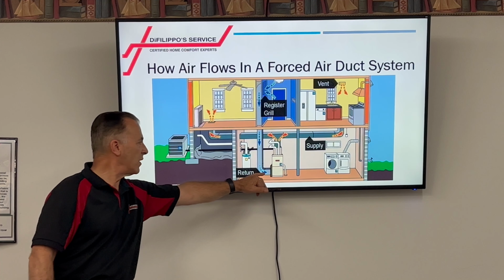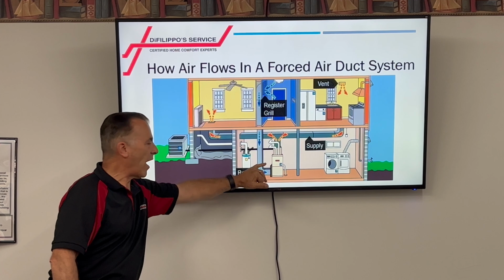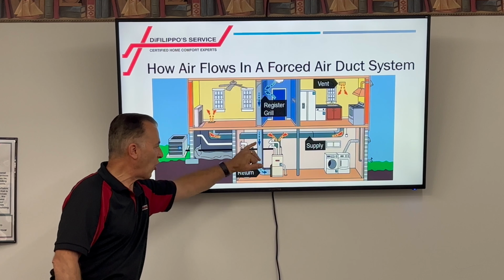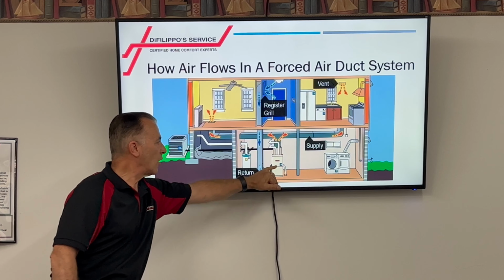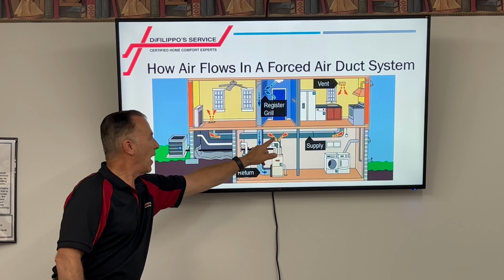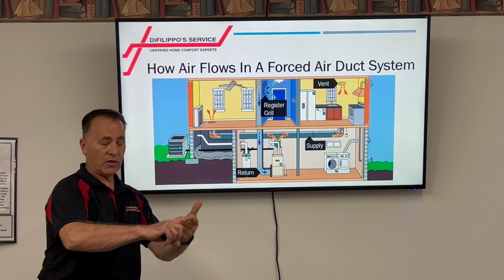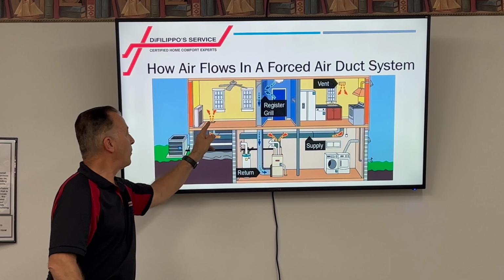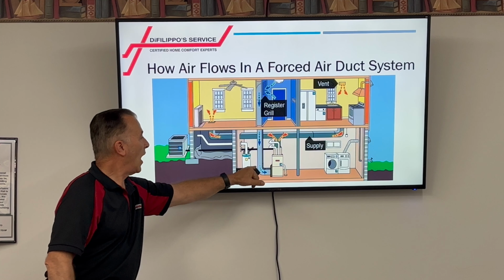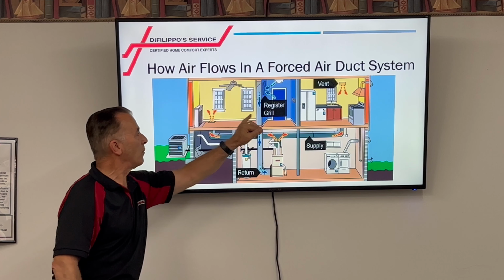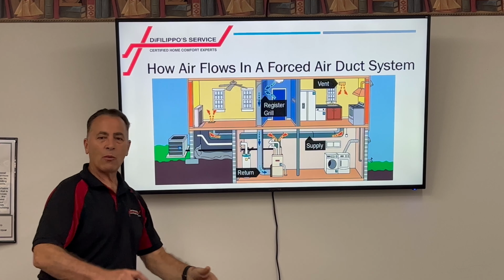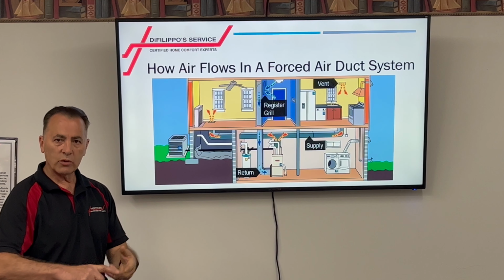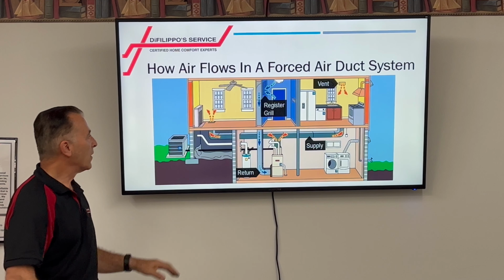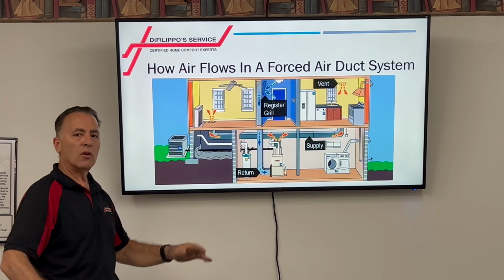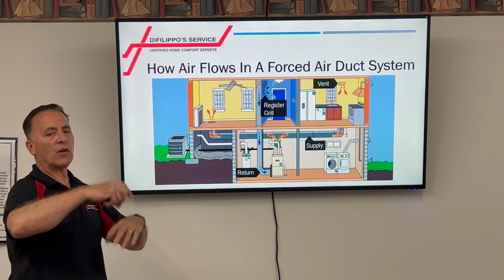How does the air go to each room? Simple. With your furnace being in the basement, the return air, always think return, I'm returning air back to my furnace, where it either gets heated or cooled and then sent on its way through either the square ducts or the round ducts up into each individual room. And then the return picks up air from each individual room, brings it back where it's either heated or cooled, and sent on its way. That's why it's nice to have a return in each room, so we're taking out the heat, taking out the cold in each room.